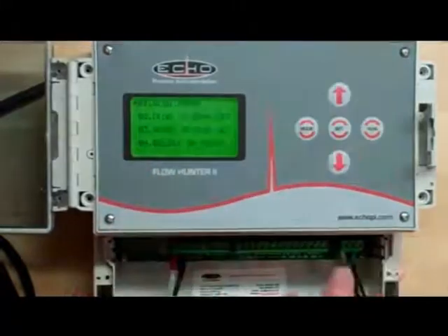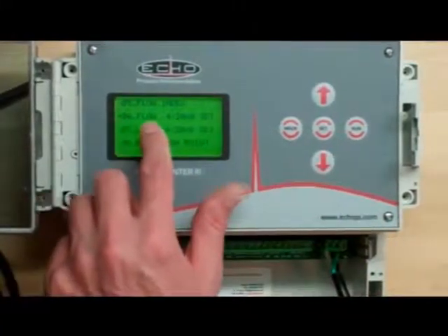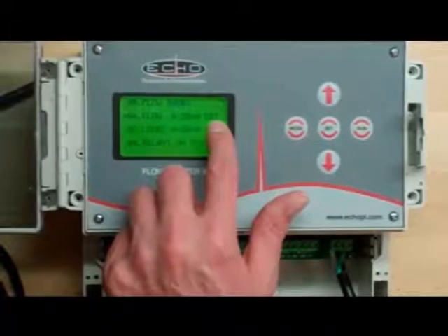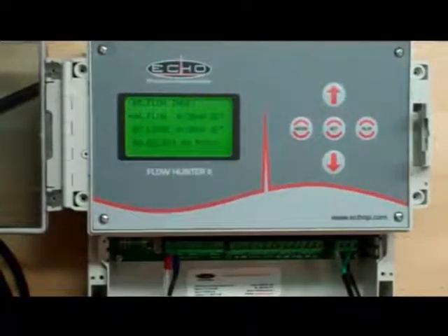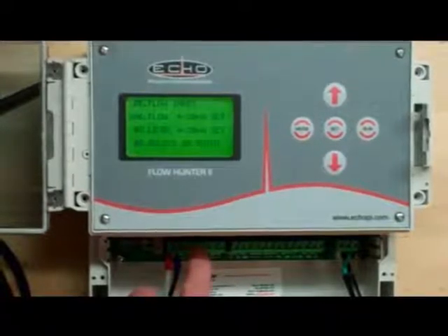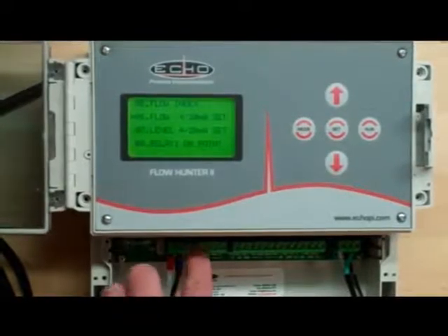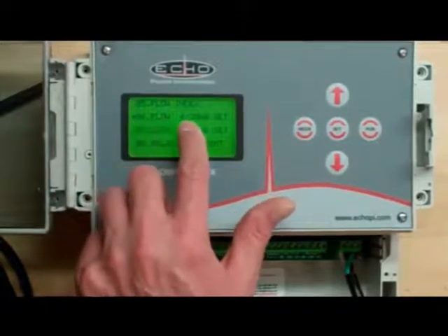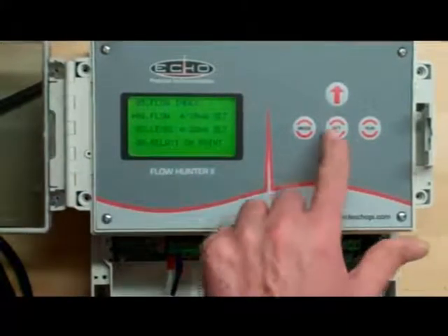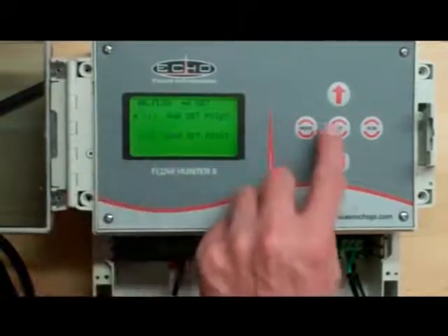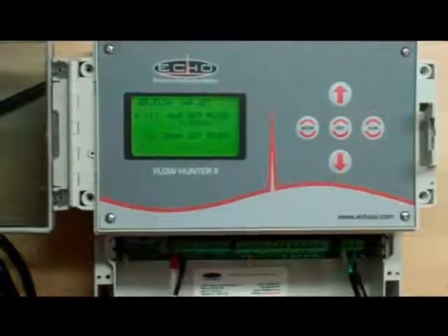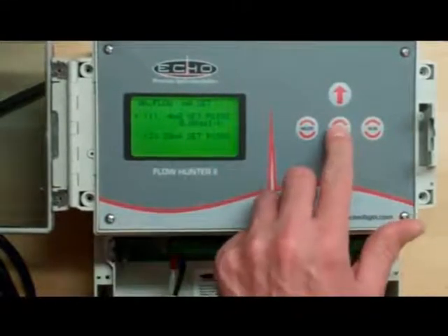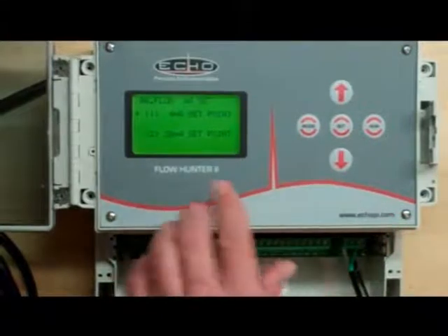The number goes away. Now we're going to move down to number 6, which is your flow 4 to 20 milliamp set point. On your terminal strips, it's going to be number 4 and 5. 4 is going to be your positive, 5 is going to be your negative. Again, this is for milliamp 1 of your flow for your 4 to 20. We're going to hit set to enter. At this point you have 2 categories, the 4. So we're going to go into the 4 milliamp set point, and it's at 0, which it should be. We hit set.